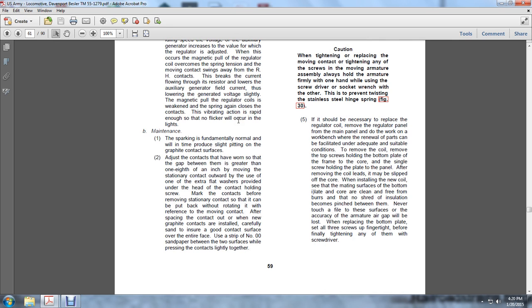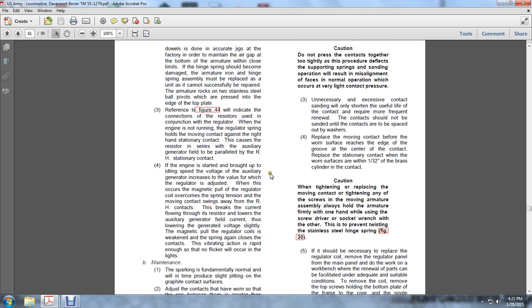B. Maintenance. Sparking is fundamentally normal, as is the slight pitting of the graphite contact surfaces. If the contacts have worn so that the gap is greater than 1/8 of an inch, move the stationary contact outward using one of the extra holding screws, marking the contacts before removing the stationary contact so that it can be replaced with reference to the moving contact. When new graphite contacts are installed, carefully sand them to ensure good contact surfaces over the entire face. Use a strip of number 00 sandpaper between the two surfaces, pressing the contacts lightly together.